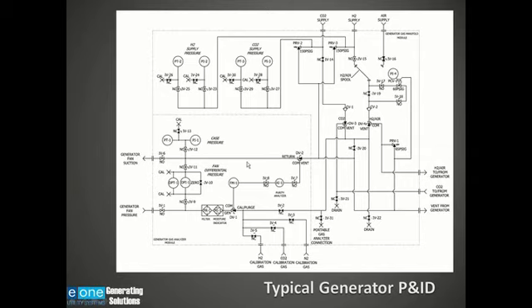So as long as the rotor is turning, I have a continuous flow of gas going through my analyzer, and I know what the purity is in that generator. If I am on turning gear and my fan is not turning, I need a way to get a sample to my analyzer. So what we do is we have to change this valve.